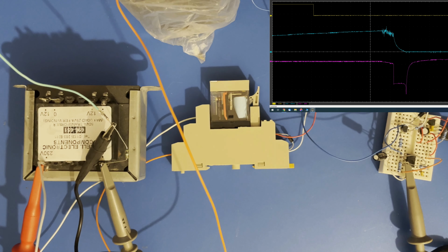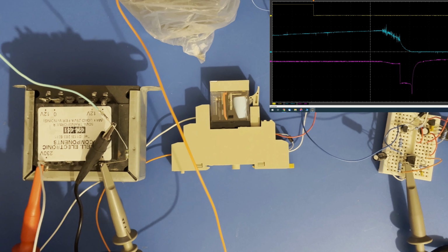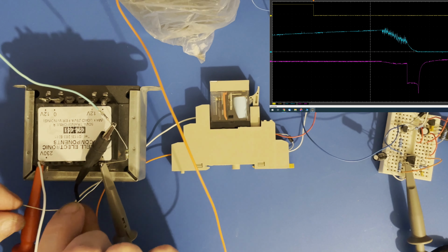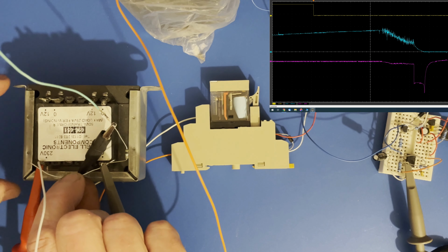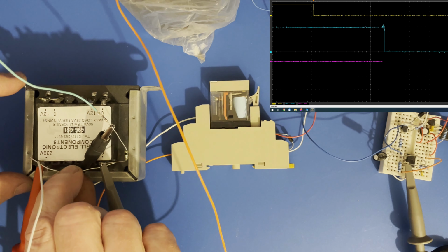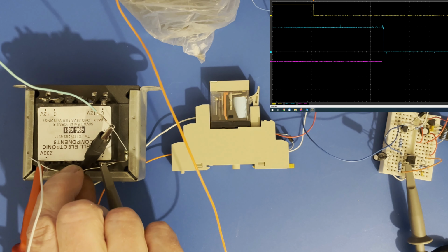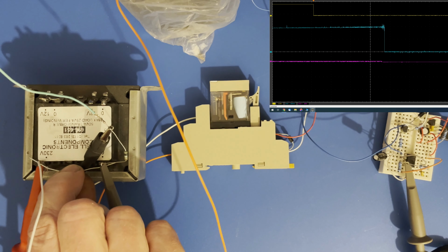there's several ways to avoid that problem, and the simplest and commonest one is a flywheel diode. I say that the current is trying to keep going in the same direction, and it can't easily when the contact opens. But as the voltage is reversing as it tries to maintain itself, you can put a diode backwards across the coil and all the nasty high voltage spikes just go away. You can see it's now a completely clean switch off.